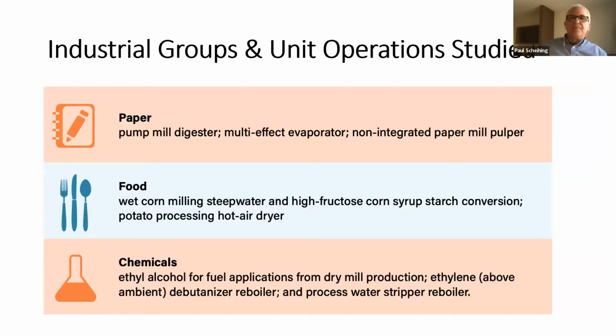Next slide, please. All right, so here we see the 9 unit operations we looked at that span across 3 sectors: paper, food, and chemicals. For 8 out of 9 unit operations, we had access to very detailed process hot and cold stream data that allowed us to perform what's called pinch analysis, to identify the most optimum placement and size of the heat pump. So the process data available to us influenced the type of unit operations we selected, along with a lot of industry input on what they viewed as the most ideal processes to potentially apply the IHPs. We created 2 levels of heat pumping in our analysis.